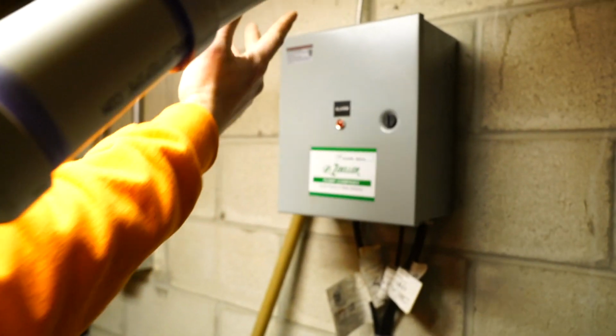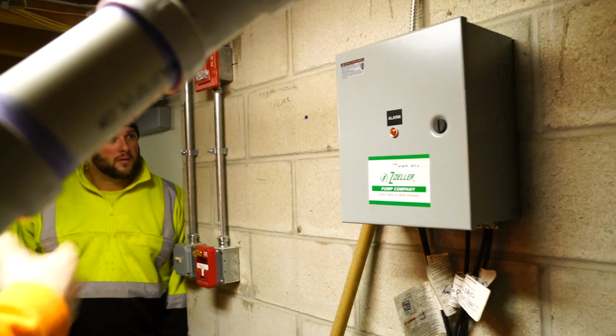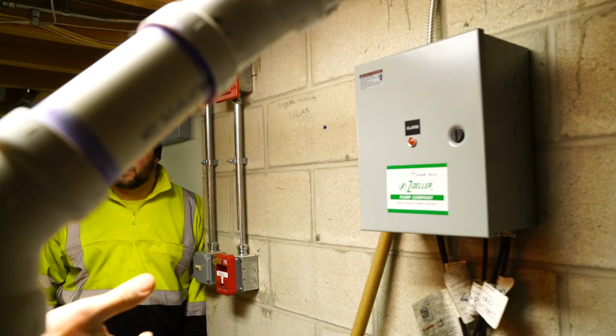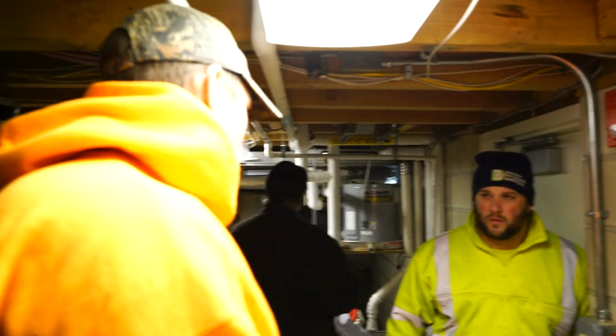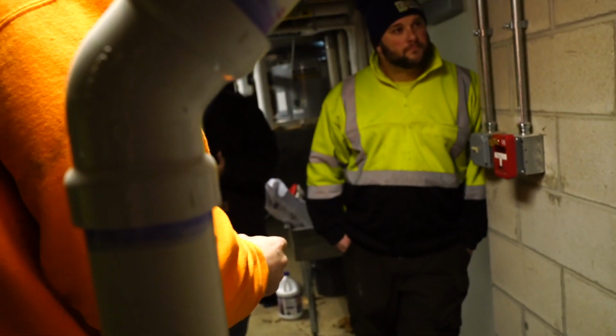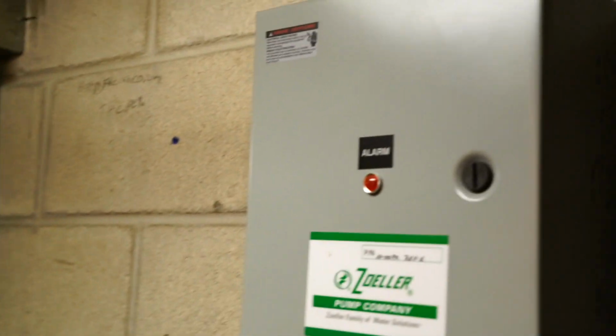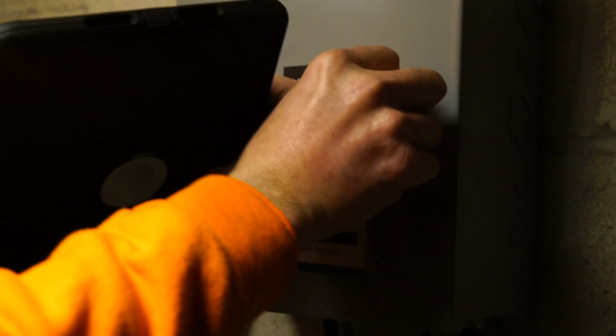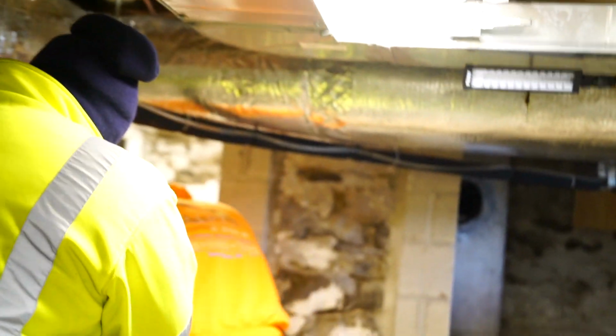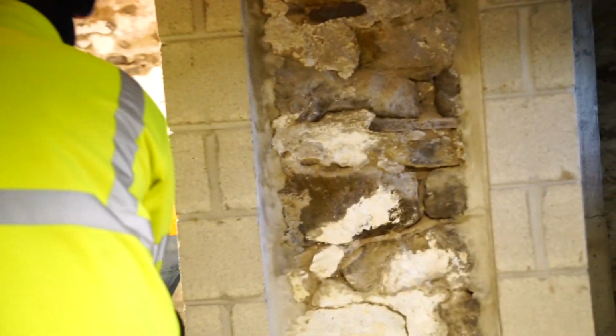If your alarm does go off, you're down here. Say there's a mechanical misfire and it's going off, it's not actually for water. You have a little silencer on the side, just to shut off the ambient alarm. Also right outside here you have another hose bib. That's your valve for your hose bib underneath there. All right, so your main water coming into this building, right here. Shut that off, and all done.